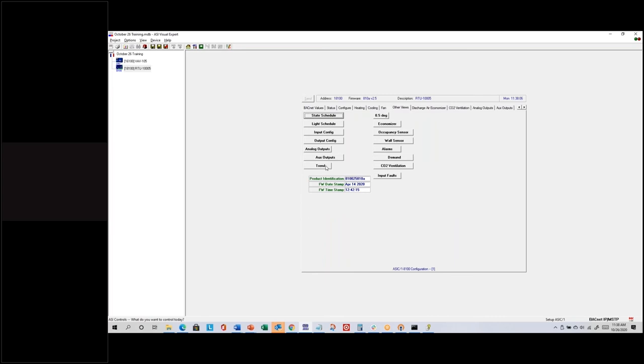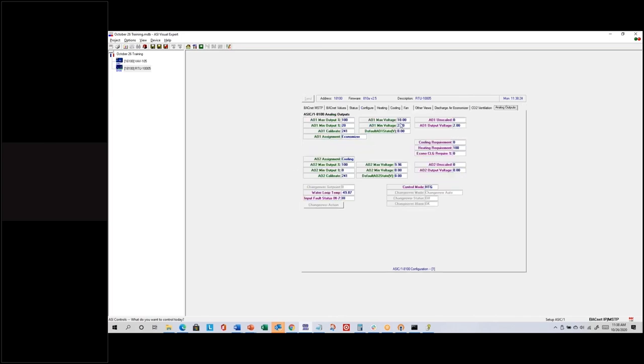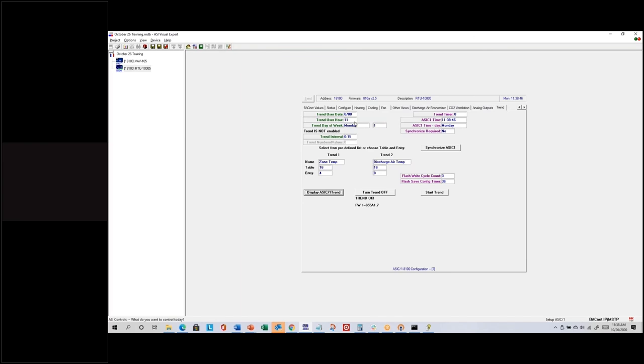The trending setup in the 8100 is the same as in the 6100, just laid out a little differently. Set your table and entry. By default it tracks zone temp and discharge temp — if you like those, just click the start trend button. Then go back to the trend tab via other views and trends — it will have set the trend day of week and hour to organize the timestamp. The interval can be as frequent as every 15 minutes.